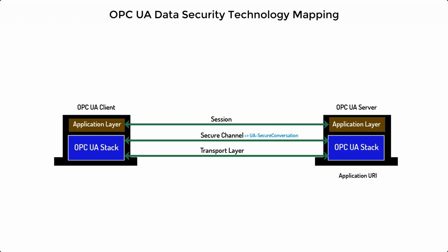For example, to reach Google search server, you use HTTPS followed by www.google.com, with HTTPS representing the transportation protocol. Now, here's the kicker. An OPC UA server is capable of implementing more than one transportation protocol, meaning that there could be more than one protocol option to get to an OPC UA server. Those options are what are called OPC UA server endpoints. For example, a server could have a TCP endpoint and an HTTPS endpoint. Now, as you would imagine, these endpoints could have different security mechanisms.